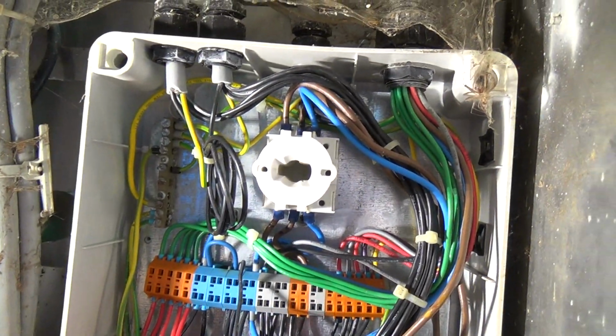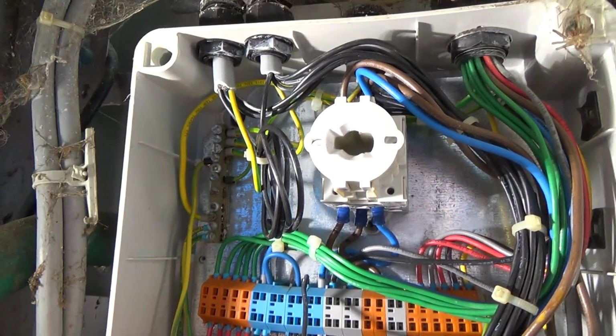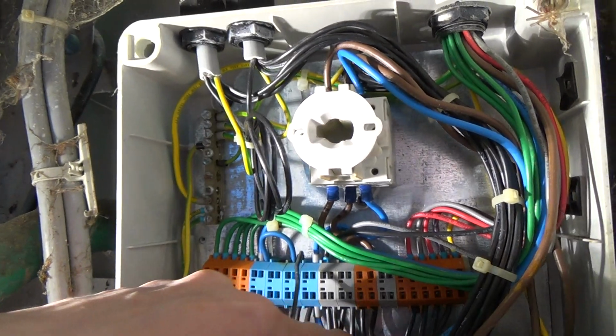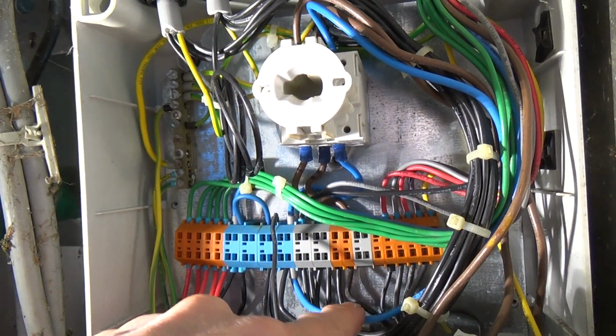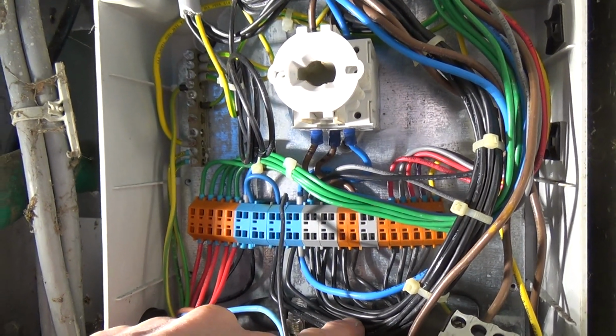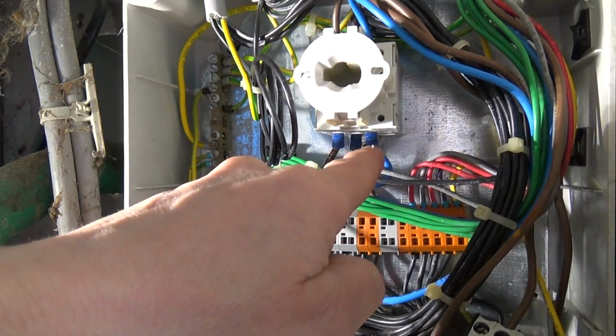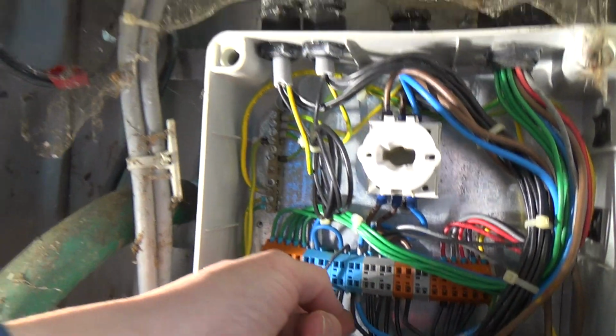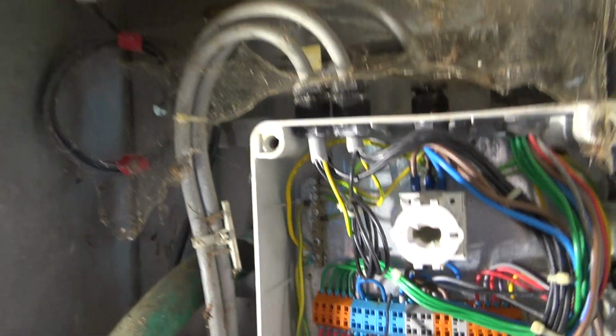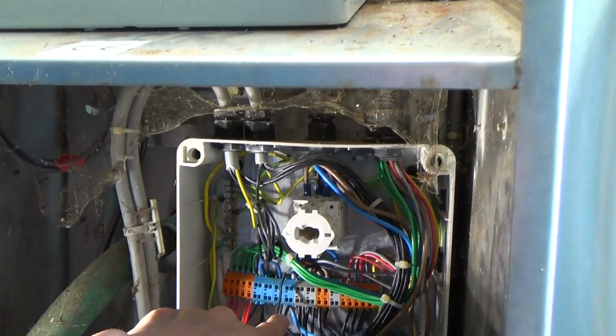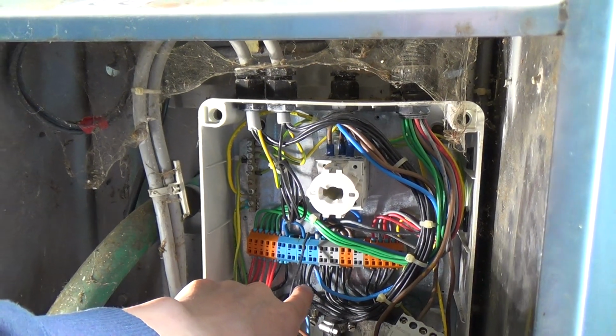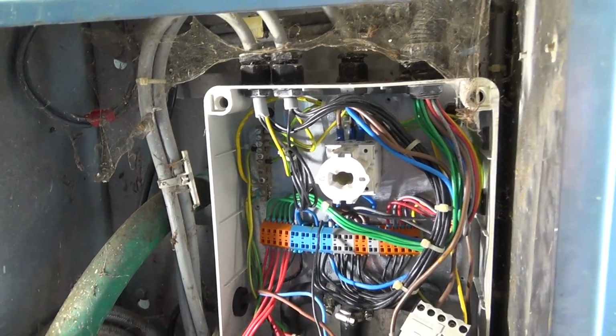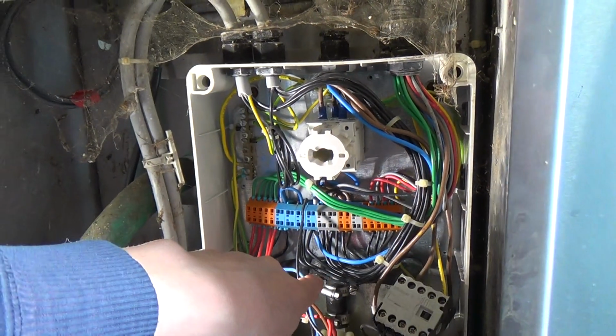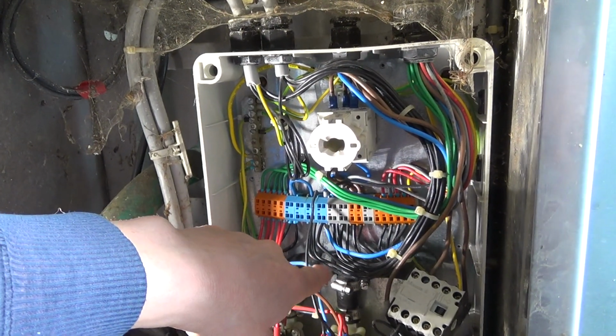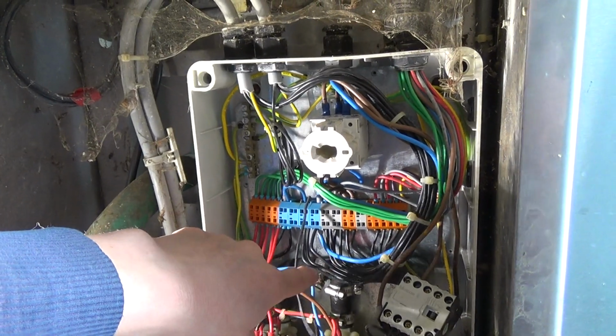And what I'm looking at here is our incoming neutrals. That's our incoming wires here. I think they're the lives. These 2 are live. So they come in on these multi-core black wires. Well, the neutral also comes in on them, and then it goes off of that blue into there, which is this one here, but this is also dabbed in there as well. So the neutral should be switched, but because this isn't done right, I don't think, we might be just meggering all the way back to the main neutral on the incoming live supply, and that will always show an earth fault, because out on the transformer where the pole is, where the power comes in, they connect the neutral to the earth, so that the neutral is always the same potential as the ground you're working on.